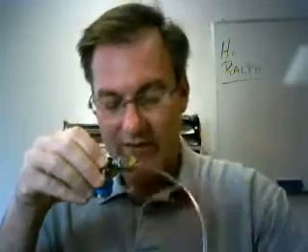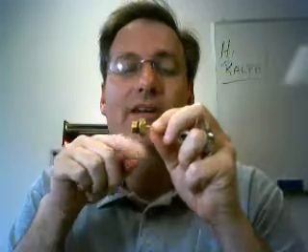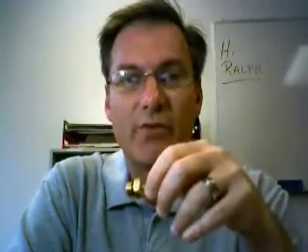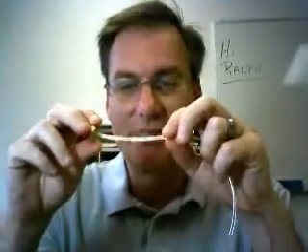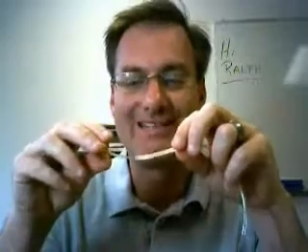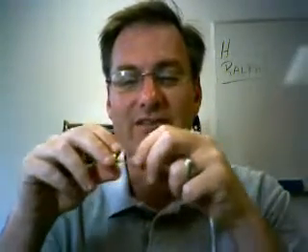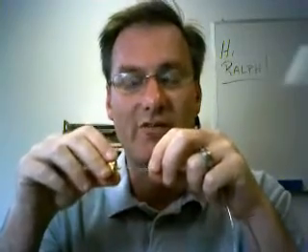We've addressed that with this little fitting — it's replaceable. It knocks pressure down from about 70 PSI down to roughly 7 to 10 PSI, and slows any migration of oil. The oil then goes up into this clear tube. The clear tube is pretty generic and comes as part of this assembly, but it's not like the big identifiers that have expensive replacement hoses. This is a very inexpensive part to replace and should keep your identifier working great.